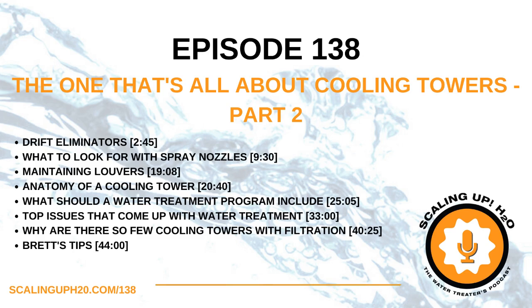I'm curious, how has your life as a manufacturer changed since ASHRAE 188 came out and was adopted by New York? We get a lot more requests for tower information because they have to register all their towers in New York City now. What we've seen, which is one of the topics I wanted to talk on, is a lot more overfeeding of oxidizing biocides in units. I don't want to put this the wrong way, but I understand some places have regulations about when you need to feed an oxidizing biocide, and to what residual if you get a test count over a certain range. But I think some people are taking advantage of that, feeling they can overfeed just to make sure they're not having that bacteria count.